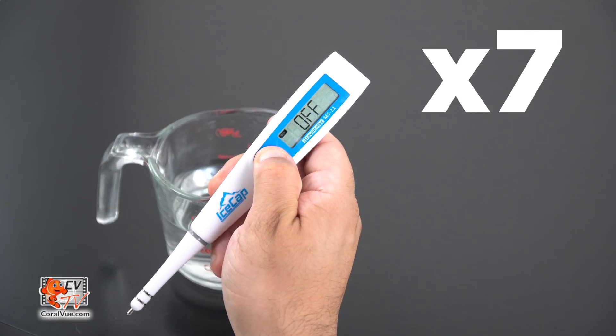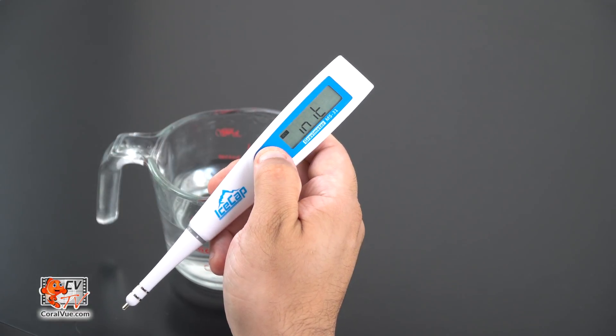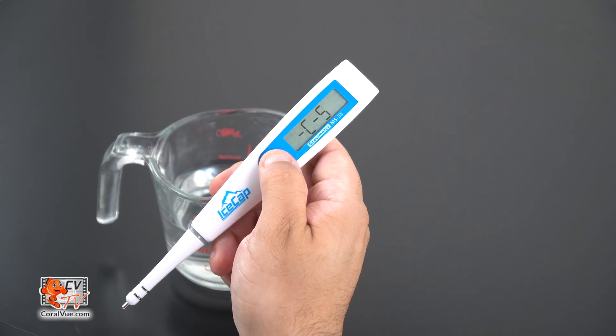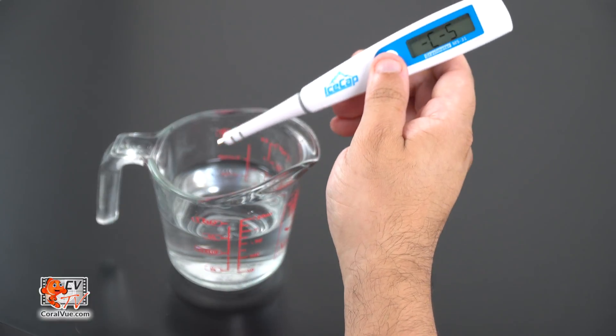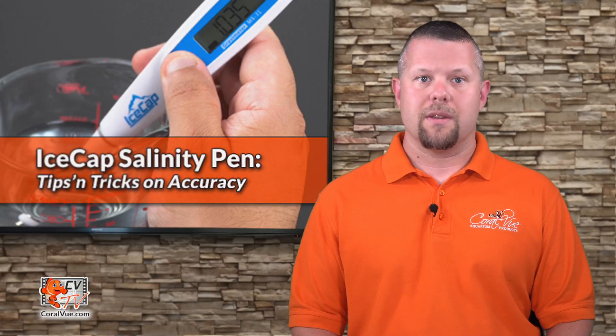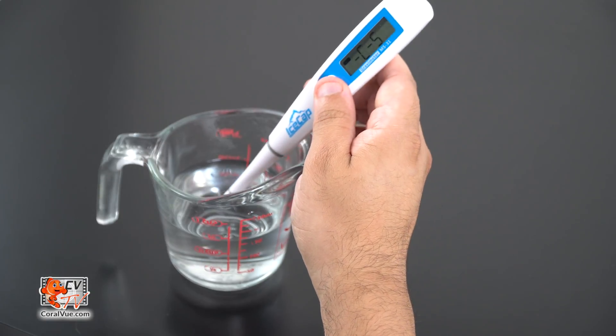With the pen off, click on the power button seven times quickly. It will turn on the screen and will display a CS. If you do not see this, then try again. Submerge the tip of the pen in the calibration solution.